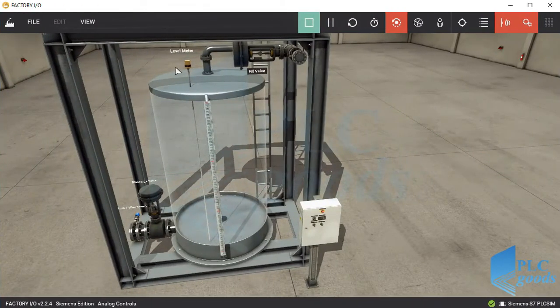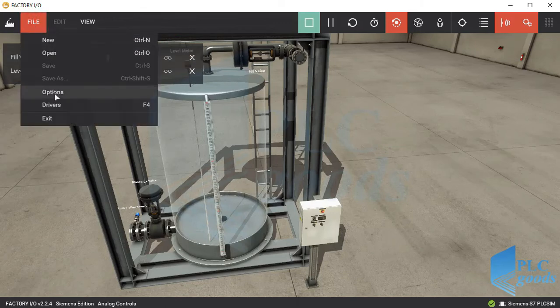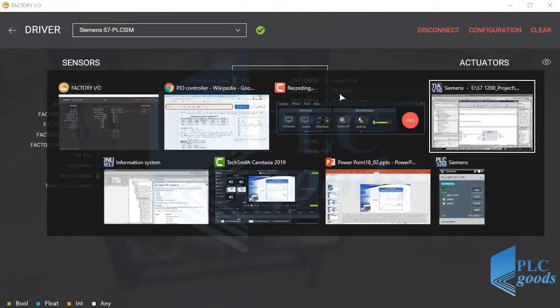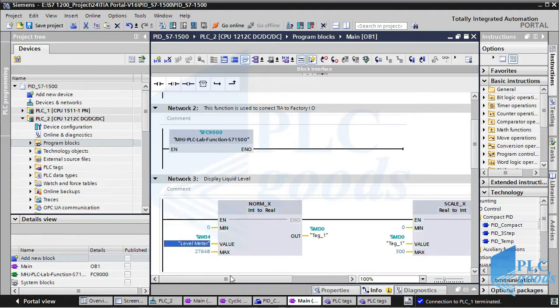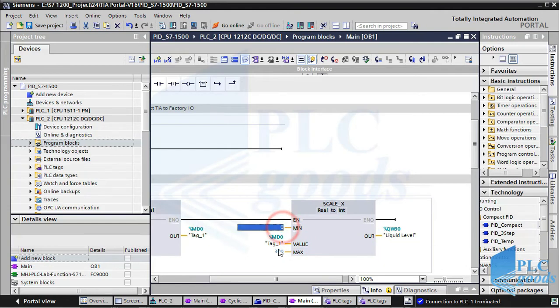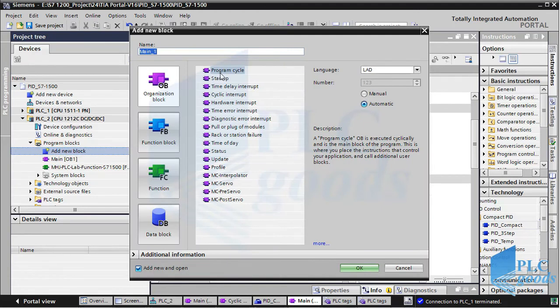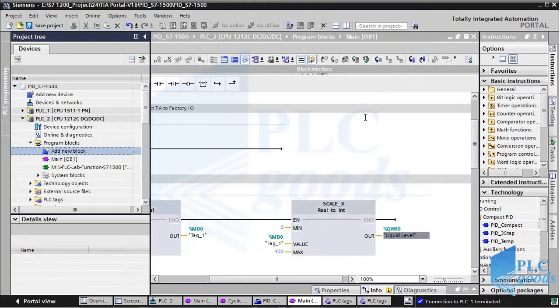Now let's design a PID controller in TIA Portal. Here we have a level meter and a valve which are connected to PLC addresses. The second network of the PLC program converts the level sensor signal to a number between 0 and 300, indicating the liquid level in centimeters. The easiest way to implement a PID controller in TIA software is to use the PID instruction. To use this instruction, first click on 'Add New Block', then select 'Cyclic Interrupt' and set its time to 500 milliseconds. This organization block will be executed automatically every 500 milliseconds without being called from the main block.